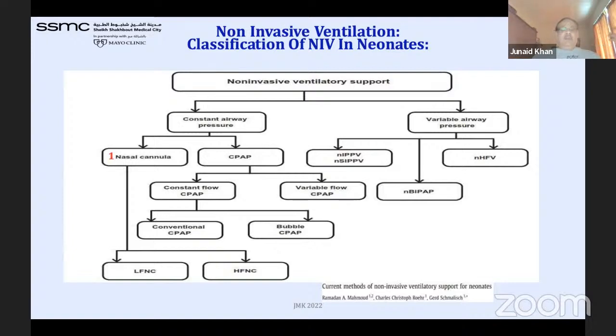So first is the nasal cannula. Nasal cannula can be the low flow nasal cannula and the high flow nasal cannula, as you can see here. Then we have CPAP, which is the gold standard of non-invasive ventilation. It has constant flow and variable flow. Constant flow, which most of us are using, is bubble CPAP and conventional. Variable flow is very few devices, like the infant flow driver or the jet ventilator, which has an interrupted wall. You can produce it. There are some studies that say the variable flow is better for carbon dioxide removal.